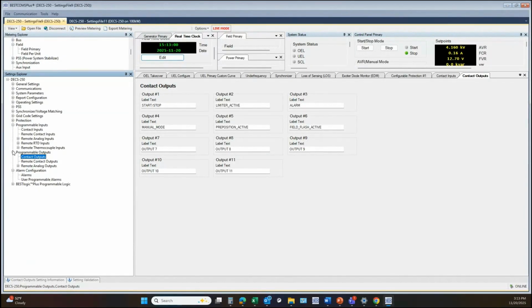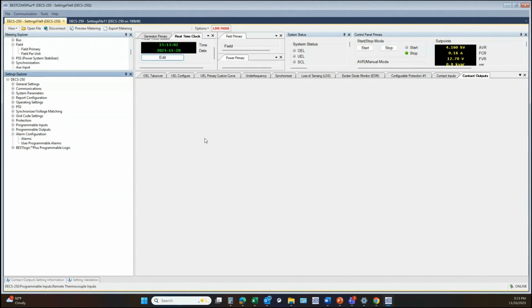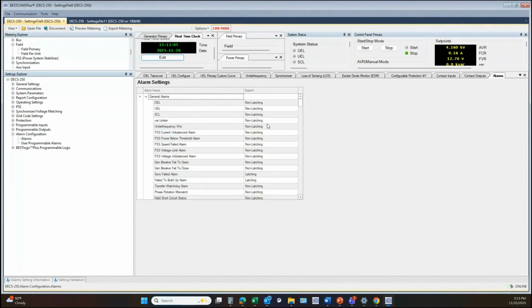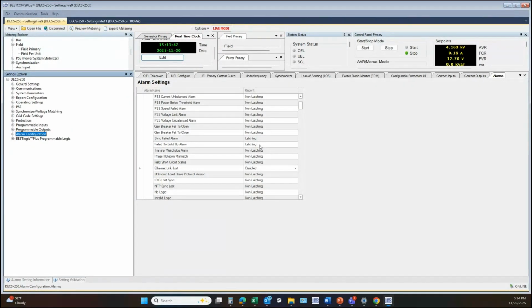And then alarm configuration, this is where most everything is enabled by default, either non-latching or latching alarms. You can go in here and disable things so that you're not getting a nuisance alarm occurring and taking up a lot of your sequence of event reports and such. For example, the Ethernet link loss, if you do not plan to use the Ethernet port, you can set that to disabled. And note, every time I make a settings change while I'm in live mode, it automatically will attempt to send that setting change to the DECS.